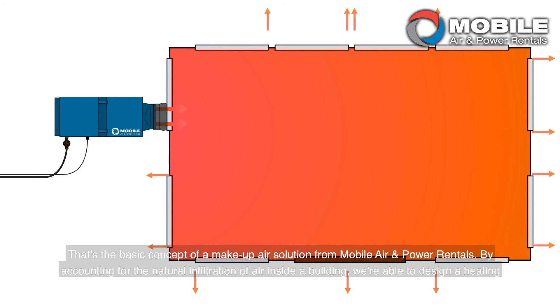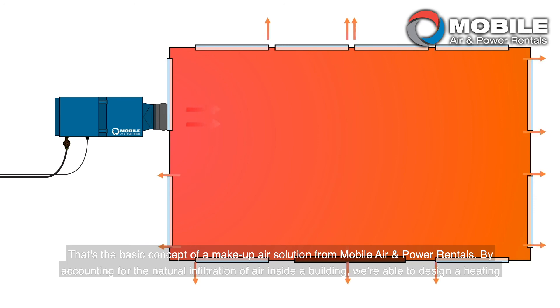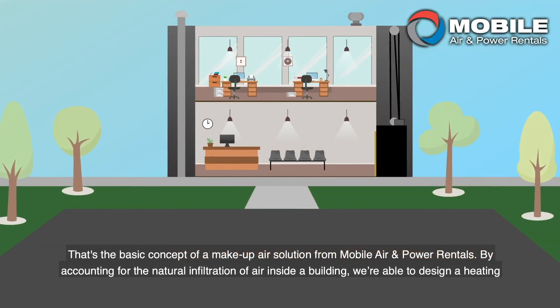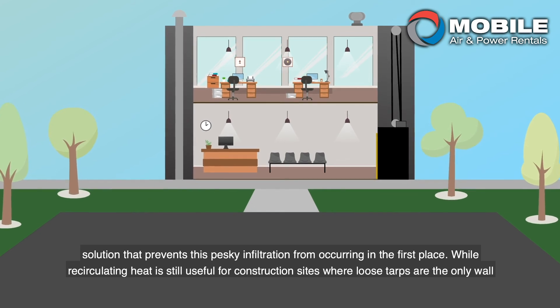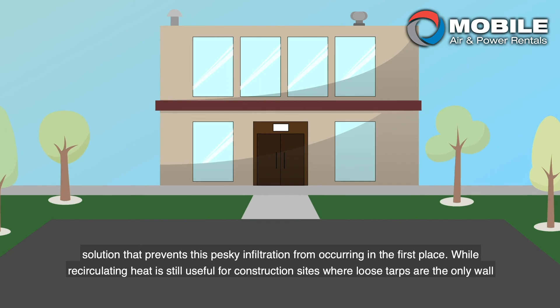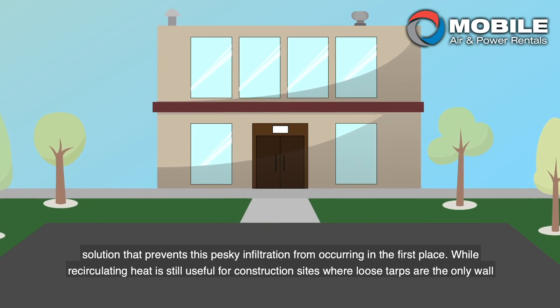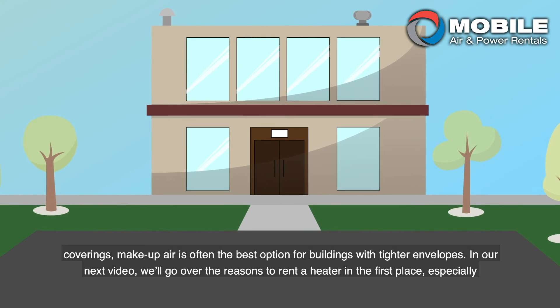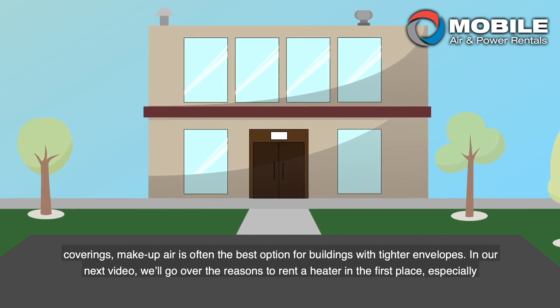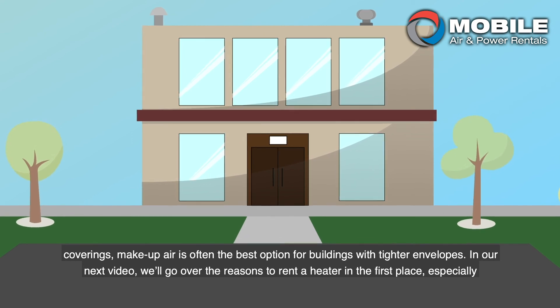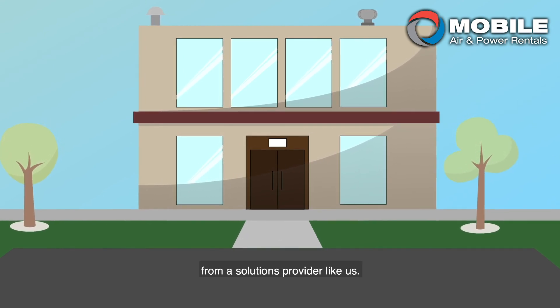That's the basic concept of a make-up air solution from Mobile Air and Power Rentals. By accounting for the natural infiltration of air inside a building, we're able to design a heating solution that prevents this pesky infiltration from occurring in the first place. While recirculating heat is still useful for construction sites where loose tarps are the only wall coverings, make-up air is often the best option for buildings with tighter envelopes. In our next video, we'll go over the reasons to rent a heater in the first place, especially from a solutions provider like us.